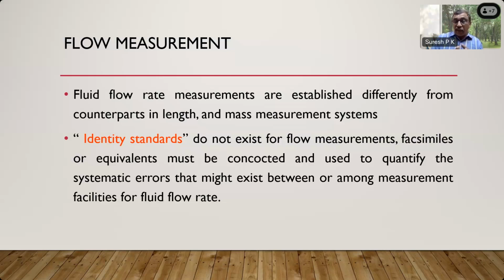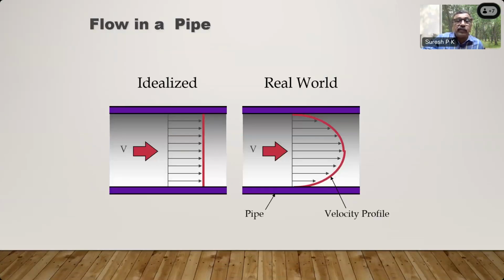Its facsimile or equivalent must be concocted. That is, you have to fabricate it and then use it to quantify the systematic errors that might exist between or among measuring facilities in fluid flow rate. That is what makes flow measurement unique from other measurements. There is no identity standard as such. Therefore, the complication associated with flow rate measurement is also more, so the probability of making a mistake is also more. That is the difference between flow rate measurement and other standards.